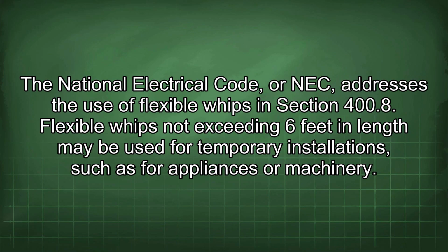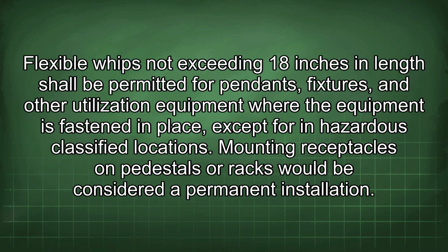The National Electrical Code, or NEC, addresses the use of flexible whips in section 400.8. Flexible whips not exceeding 6 feet in length may be used for temporary installations, such as for appliances or machinery. Flexible whips not exceeding 18 inches in length shall be permitted for pendants, fixtures, and other utilization equipment where the equipment is fastened in place, except for in hazardous classified locations.